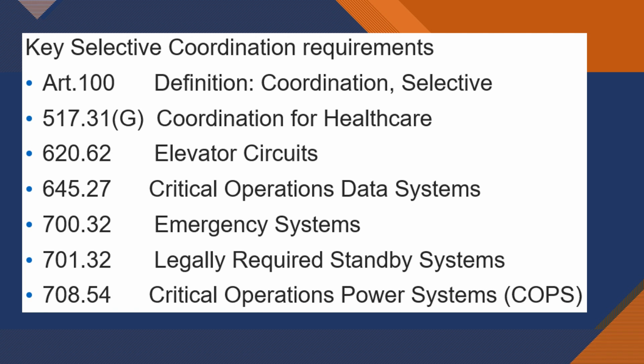So like we talked about before, selective coordination is not necessarily just found in chapters 1 through 4. It's in chapters 5, 6, and 7. The article, of course, now in the 2023 has moved over to Article 100. I don't know if it was always there or not, but it's there now in 2023. And this is kind of a general list of what it's for. Critical operation power systems. So we're talking about hospitals, 911 call centers, things of that nature.